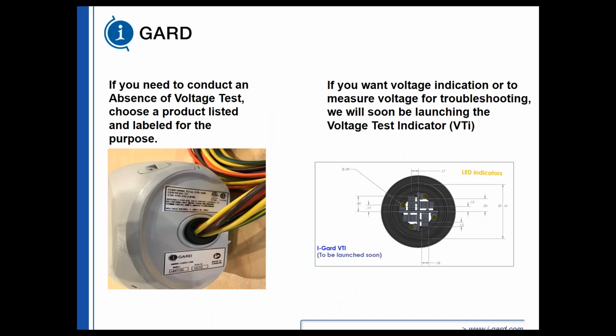So if you need to conduct an absence of voltage test, you choose a product listed and labeled for the purpose. And you can see here, it conforms to UL standard 1436. It's also certified to CSA standard C22, but the UL 1436 is the most stringent standard for the absence of voltage tester. If you still want to use a voltage portal, we have a product that we're launching in the near future, which will combine the LED lights as well as the portal in one combined unit, as well as using non-contact testers. So this device will use all three. However, it is not an absence of voltage indicator. It is a voltage test indicator and portal.